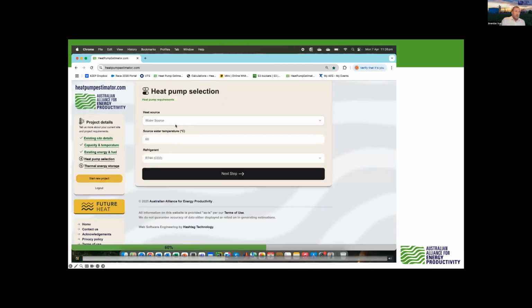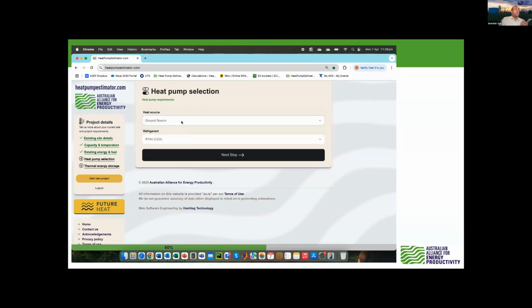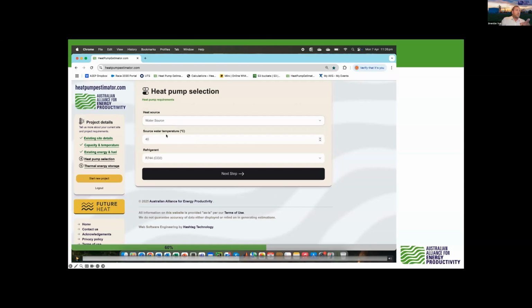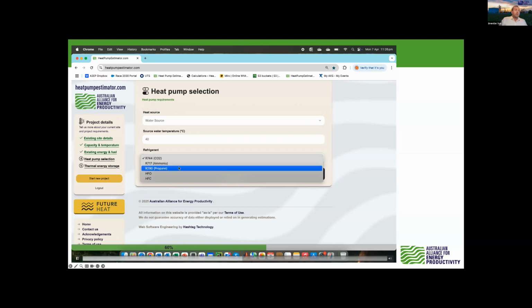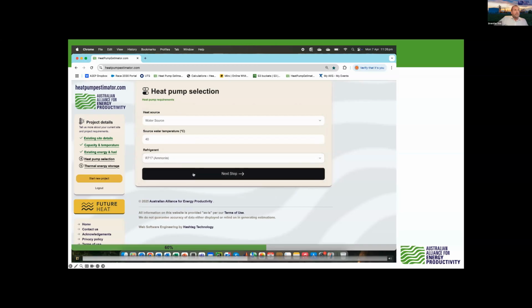So here we can choose our heat pump and we have an array of options. We have water, ground source, or air source. Kind of speaks for itself, but air source will run off the ambient temperatures for the location. Water source will run off a temperature that you provide, which I'm showing right here. And ground source will run off the pre-built input temperatures in the background of what the groundwater temperatures are specific to your location. So I'm going to choose 40 source water. I'm going to choose an ammonia heat pump. And then we're going to hit next.